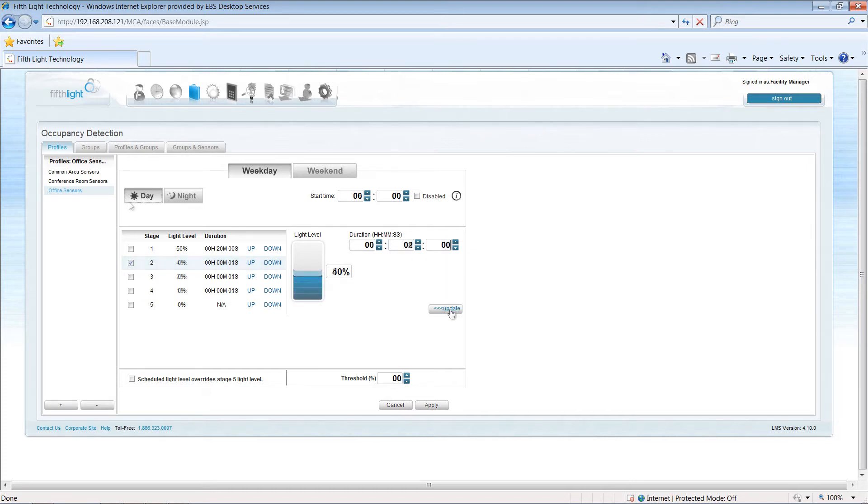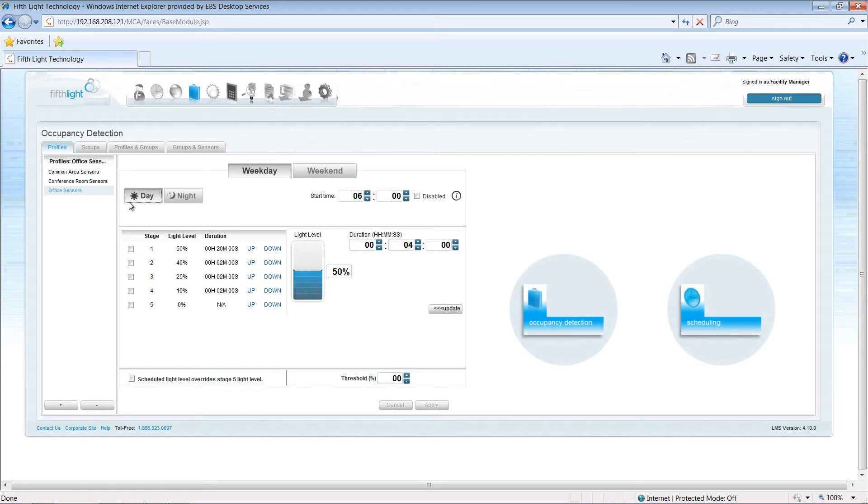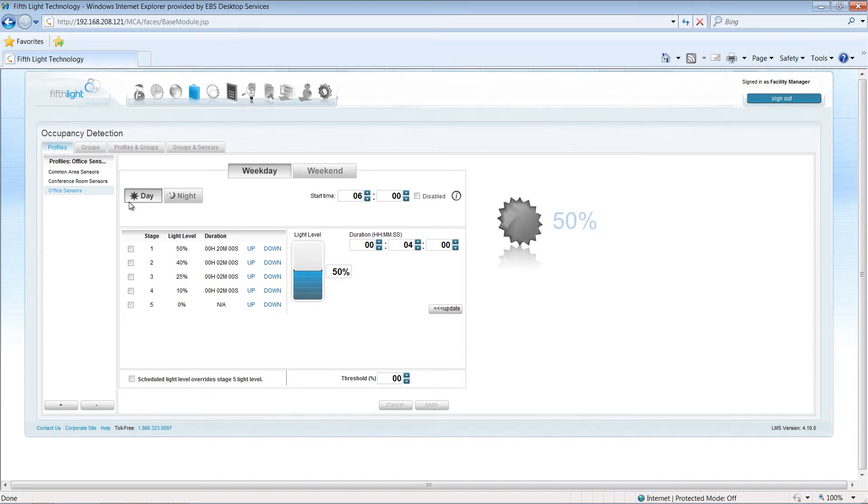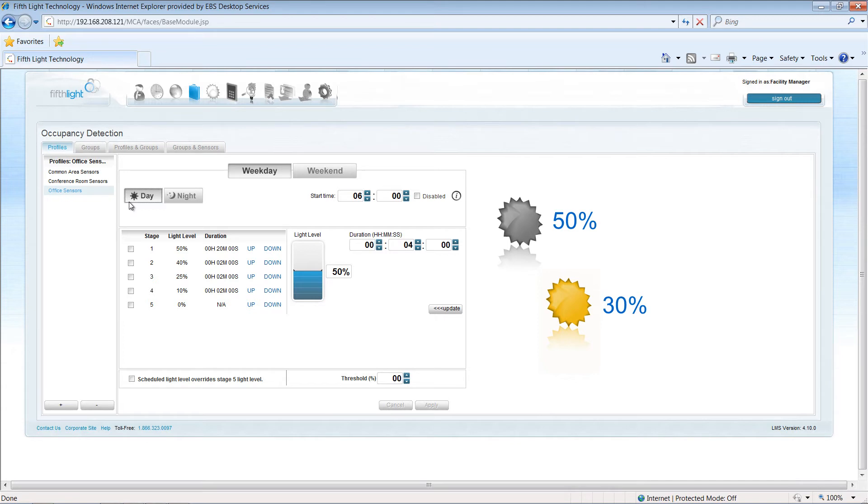In the fifth light system, Occupancy Detection and Scheduling profiles interact to dynamically change the light level that triggers upon initial detection. During the darker morning hours, I want the office lighting to trigger to 50%, but in the afternoon when it's brighter, I want to trigger to a 30% level to maximize my energy savings.